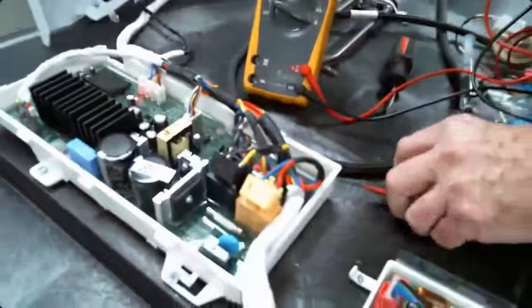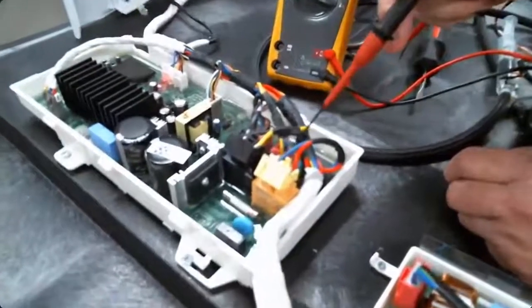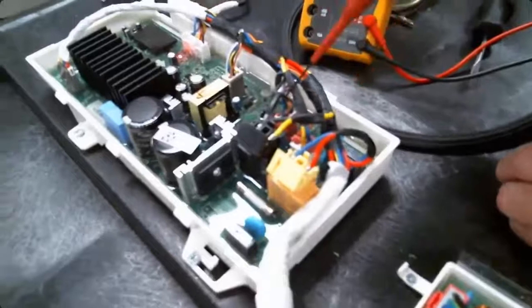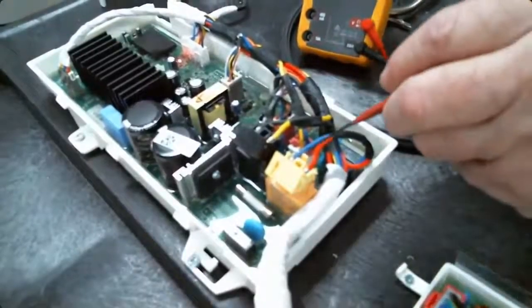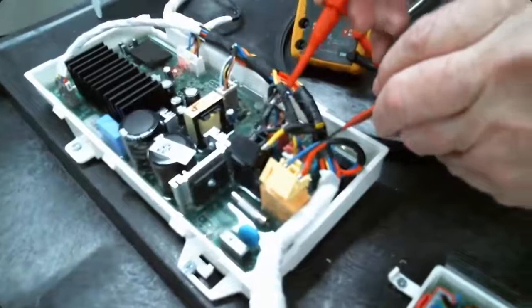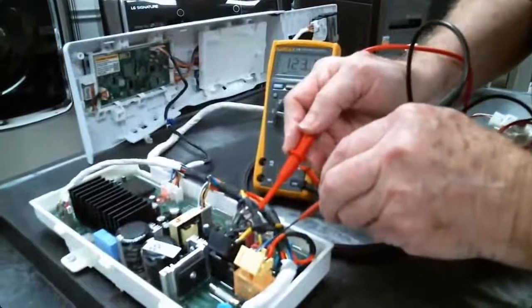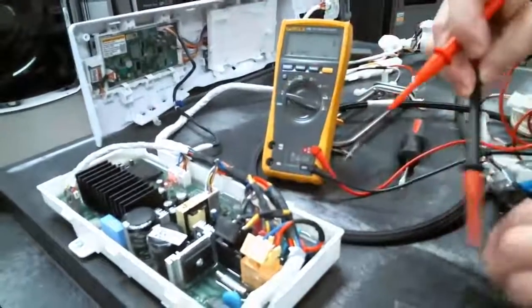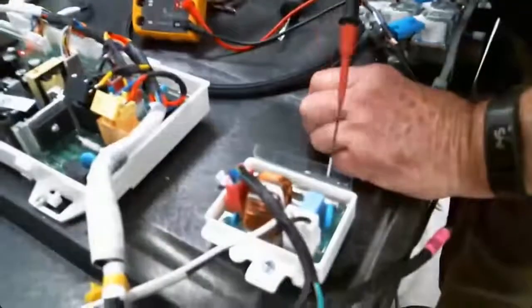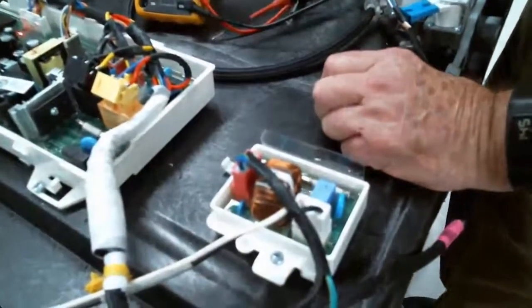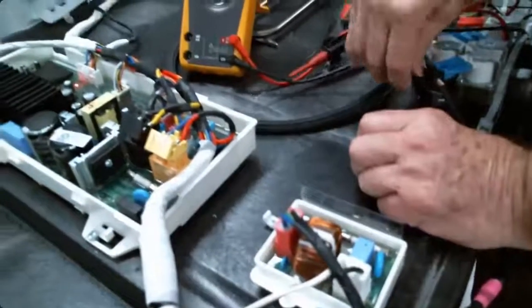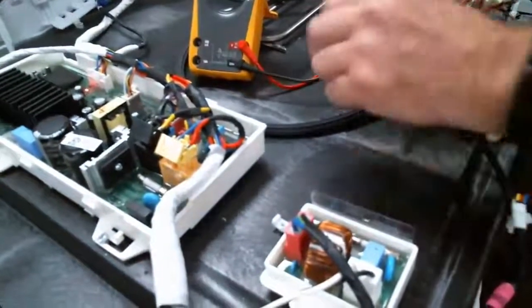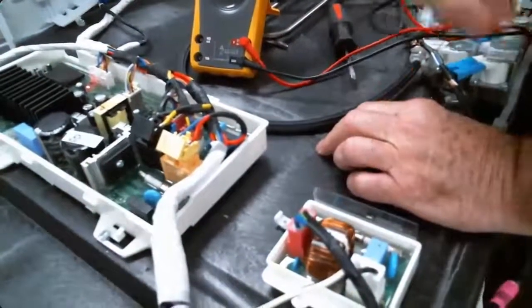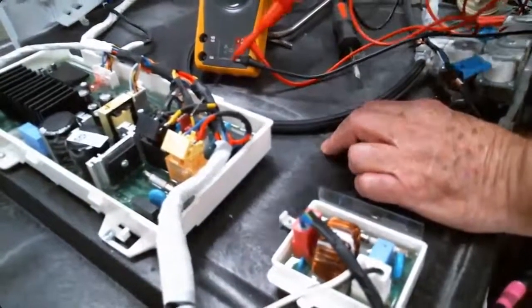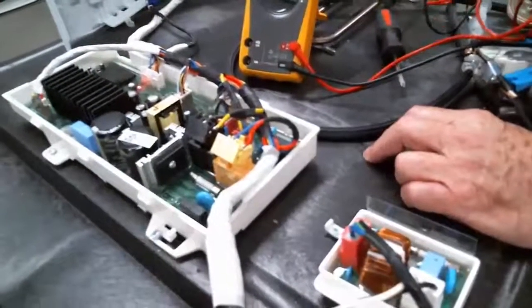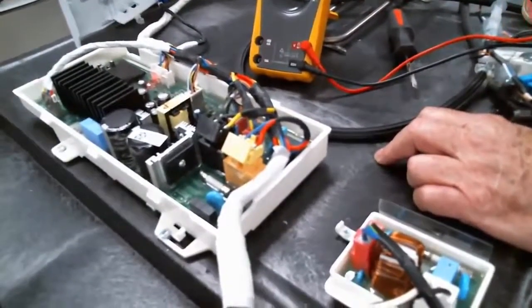So I'm going to set this for AC voltage. I've got my neutral, which is the blue wire here, and my black wire, which is my L1 wire. So we can check for incoming voltage to that - I got about 123 volts. Now you can also check that at your noise filter. Your noise filter does have a fuse, but on this one the noise filter is a little farther back and harder to get to, so you don't have to worry about whether this is good or bad, or your power cord is good or bad, because I do have incoming voltage at that black and blue wire right there.